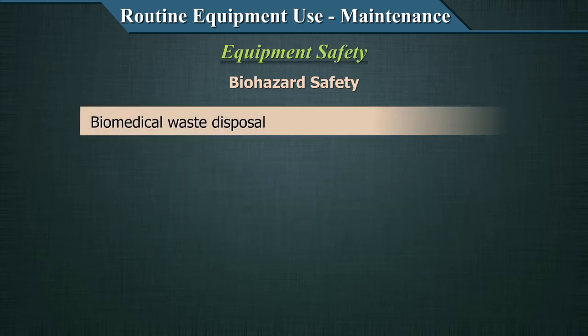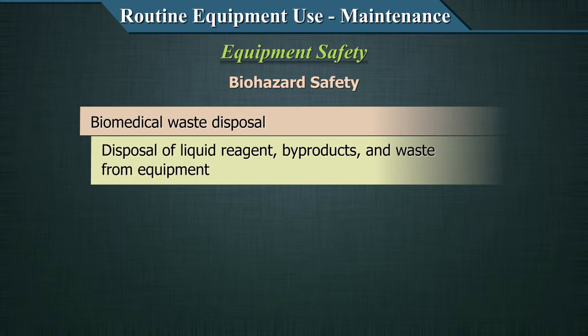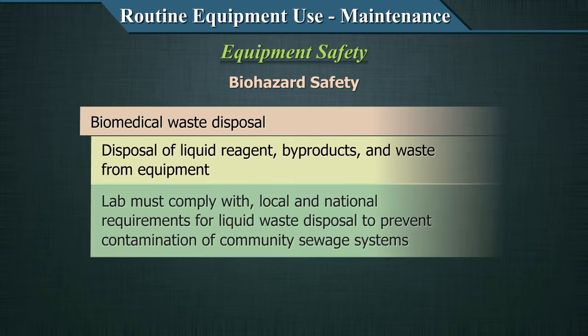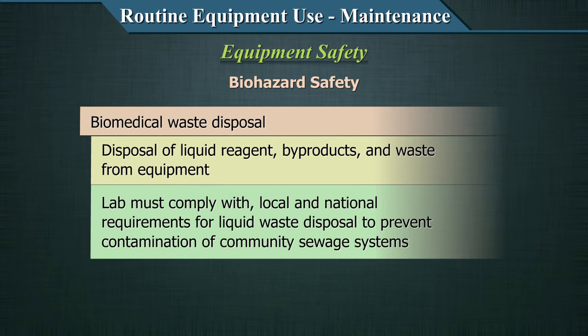From decontamination, we move on to biomedical waste disposal. Most equipment will generate liquid reagent waste, byproducts, and sample waste — all becoming part of equipment effluent. Effluent is a major concern for laboratories. When placing equipment, consider how liquid waste will be handled, and comply with local and national requirements for liquid waste disposal to prevent contamination of community sewage systems with pathogens and toxic chemicals. Effluent management is an important consideration when operating laboratory equipment.